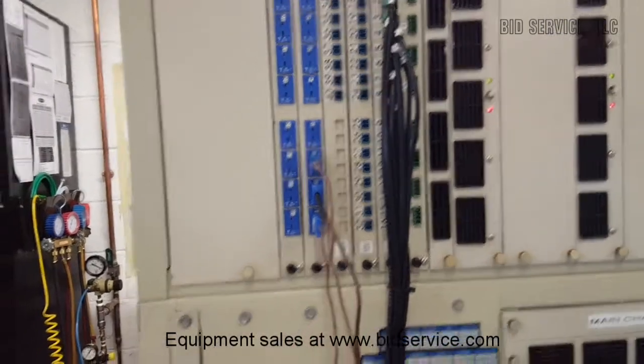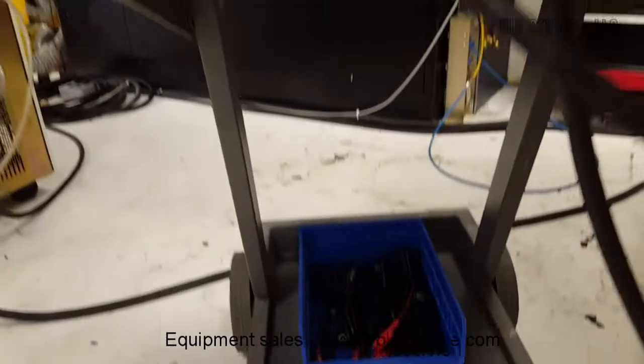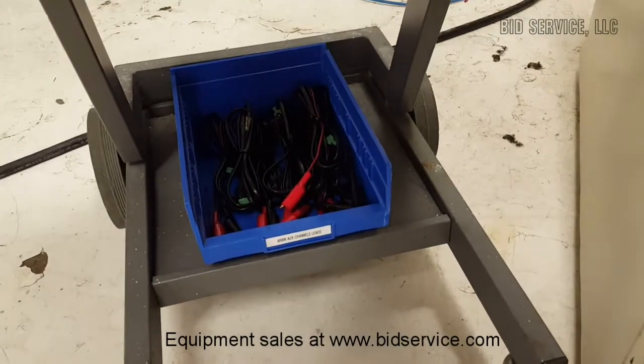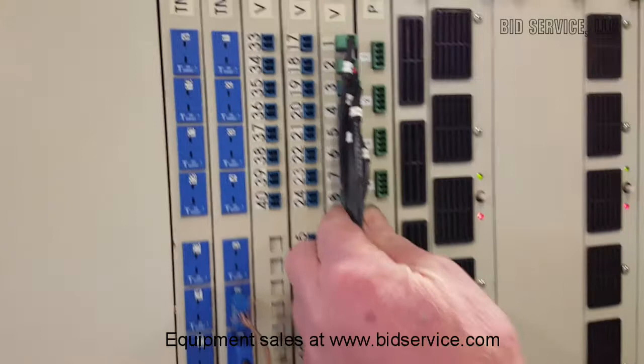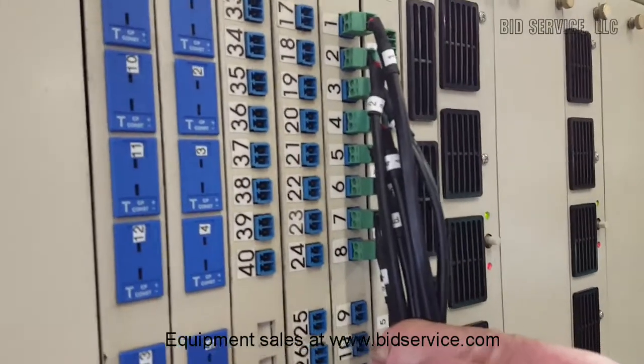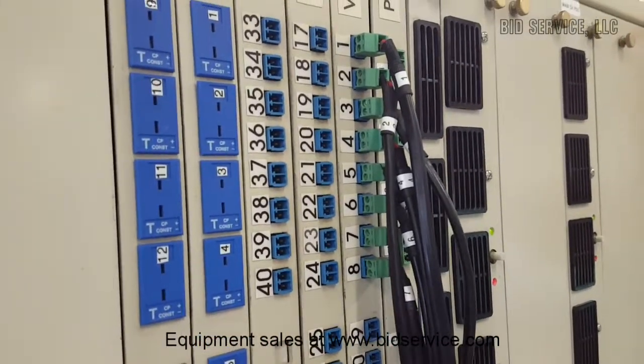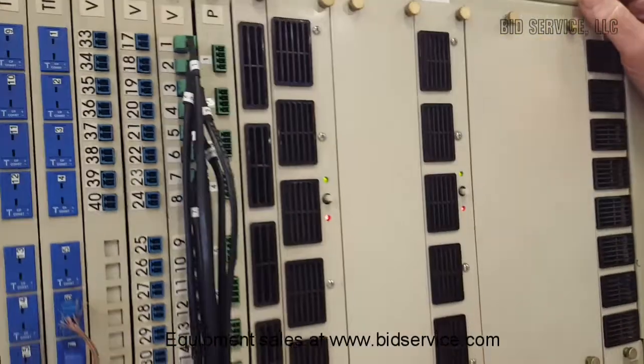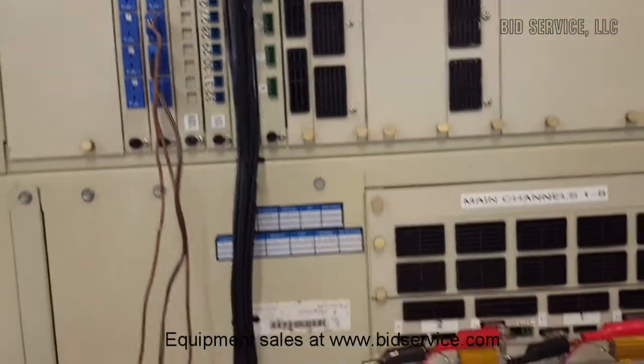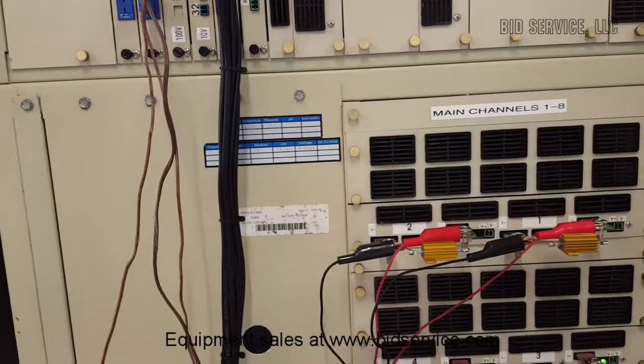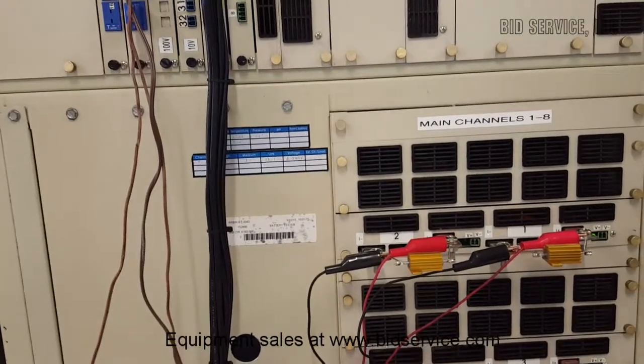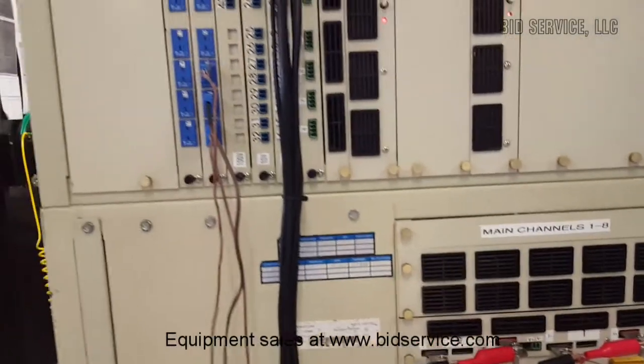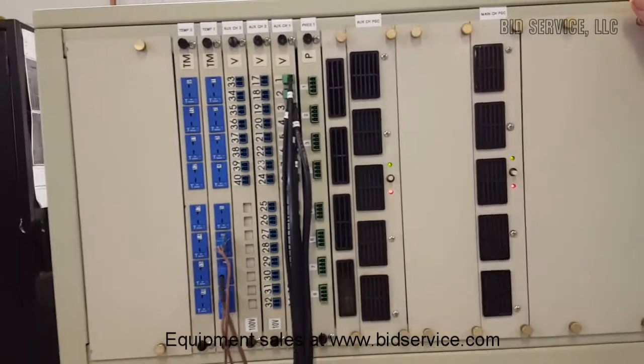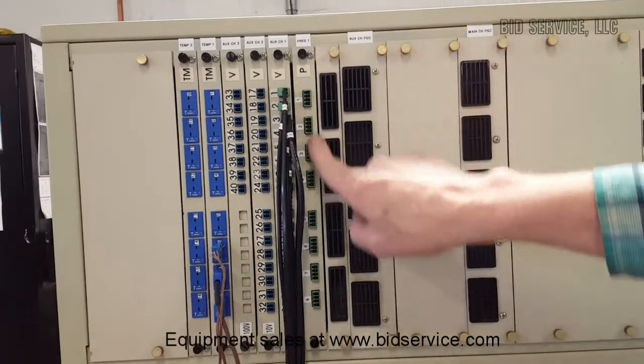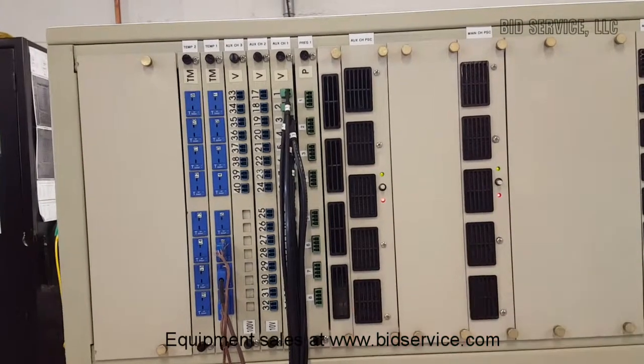We have additional leads down here that come with the instrument, but for purposes of our demonstration, I have hooked up 8 auxiliary voltage channels, and through the software I've linked them to the 8 main channels as well. If your application requires you to measure pressure, you can obtain the correct pressure transducer and hook that up here to the 8 pressure channels as well.